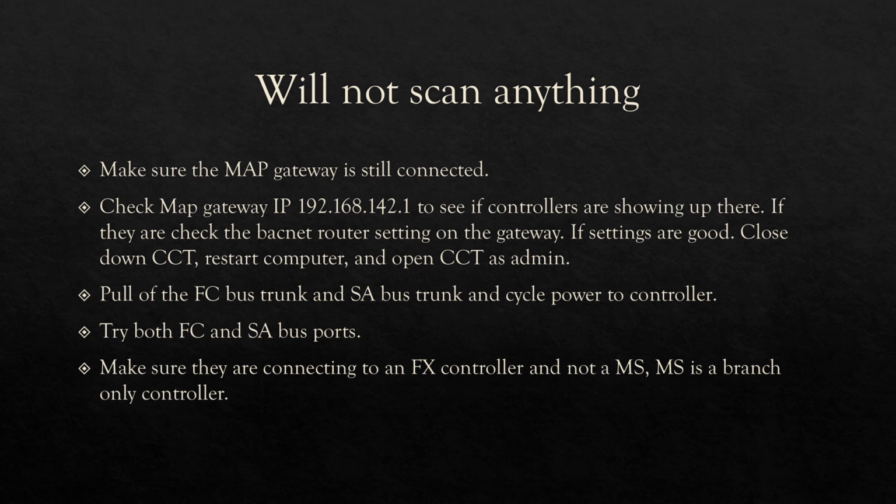Make sure you're connected to the FX controller and not the MS controller, right? If it's grayed out, you're not going to be able to talk to it. I'm saying that if it grays the branch colors, and you're trying to program a branch controller with Facility Explorer licenses, it's not going to work, okay?